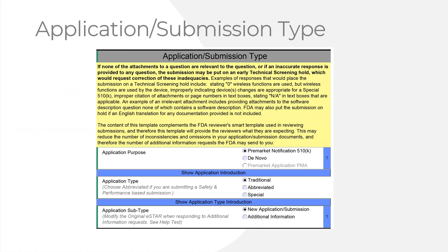For the actual submission, the way we're going to record how to do 510Ks is by breaking it up into the new sections in the eStar. In the first section at the very beginning of the eStar template, it asks you what type of submission it is. Most of the eStar template is blank until you answer those first questions. As soon as you decide whether it's a pre-market notification 510K or a de novo, the template expands very rapidly, asking a whole bunch of other things.